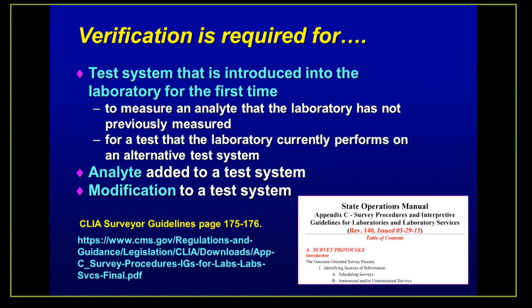Just an aside, verification is not required if you're just having routine maintenance or repair done. If you're moving your system from one location to another location in the laboratory, the CLIA does not require a verification, but it does suggest that you do a day of QC testing immediately after the move and before you start releasing patient testing.